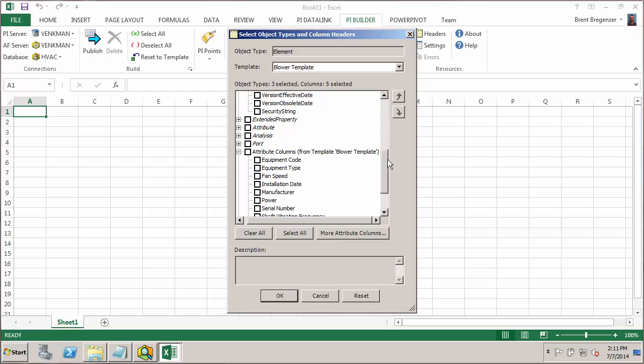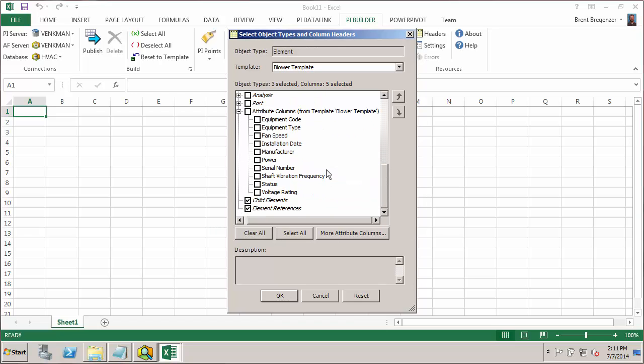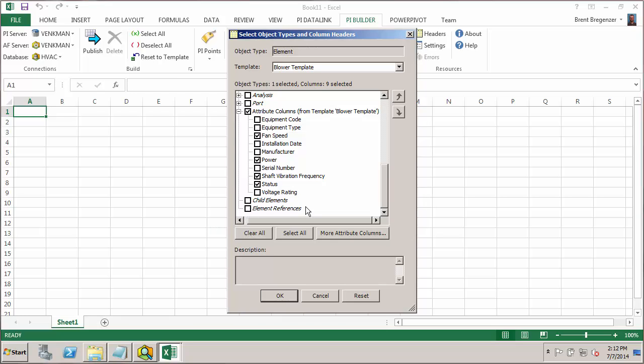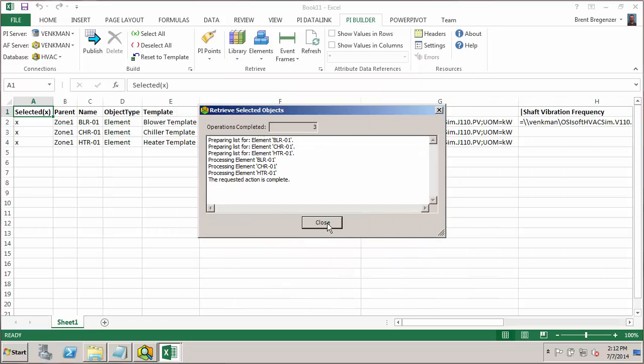What we will want to do is import attributes as columns. So here, since we are starting with one of our templates, it's showing me everything under the blower template. And all of our table lookup data references can use the same format that they've been using. So we don't need to make any adjustments to the configuration string for those. What we want to do is grab all the attributes that use a PI tag, because we know we need to specify the correct PI tag for each attribute. So those would be fan speed, power, vibration frequency, and status. And then we'll go ahead and uncheck these other two that we don't need. And finally, we have all the columns we want to specify. We can just hit OK and everything gets imported.